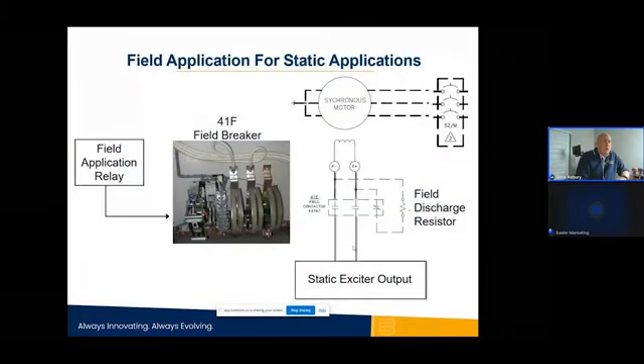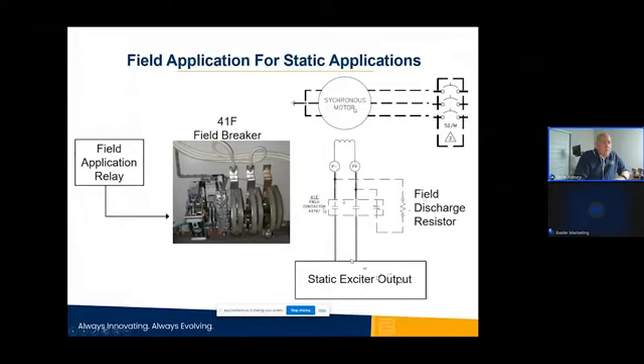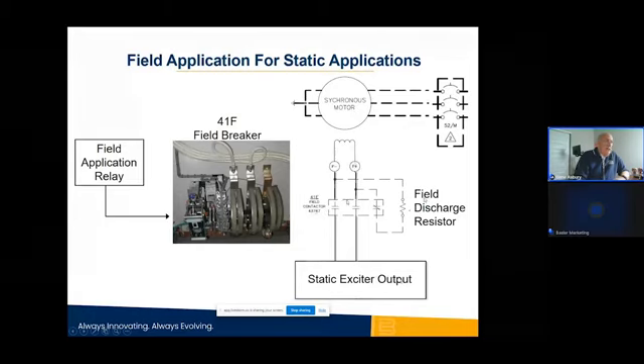So in this application, you would have the synchronous motor, and you would have some sort of a static exciter, a DC power supply, or what, back in the day, they would use like a DC power supply, ready to supply excitation to the field winding. And then you would have a field breaker, which is schematically noted here. And then you would have some sort of a relay, a field application relay, telling the field contactor to close. And you also have a field discharge resistor, sometimes they'll call that a starting resistor.